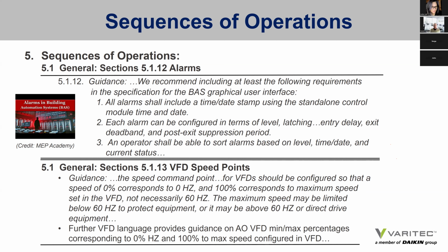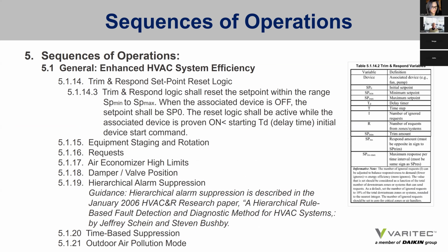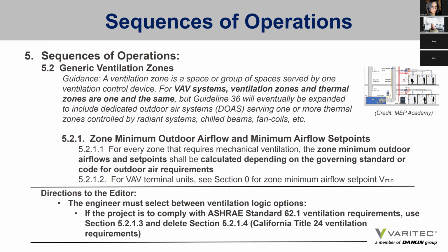And then it goes on to actually address the efficiency of a system by addressing trim and respond set point reset logic. It goes on to discuss equipment staging and rotation requests, air economizer high limits, damper valve positions, hierarchical alarm suppression, rather interesting concept I don't have my head around, time-based suppression, and outdoor air pollution mode. The sequences go into generic ventilation zones.